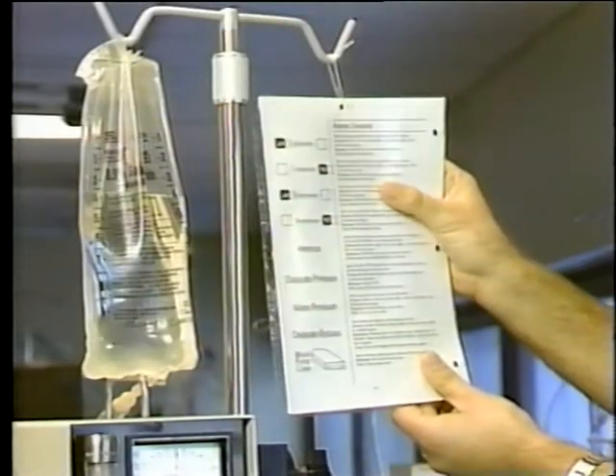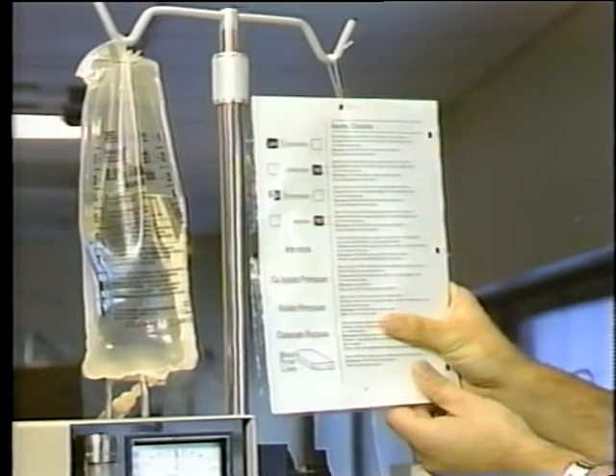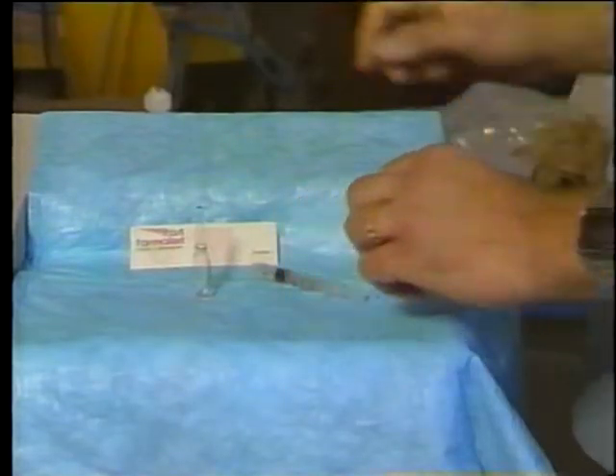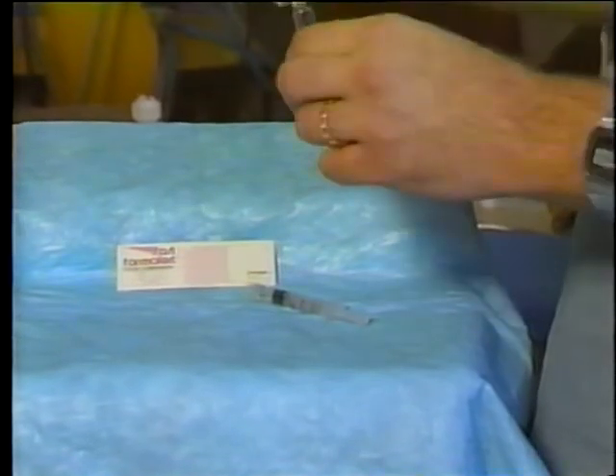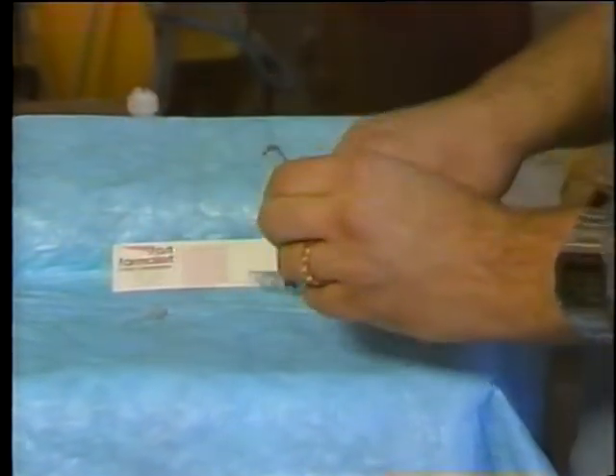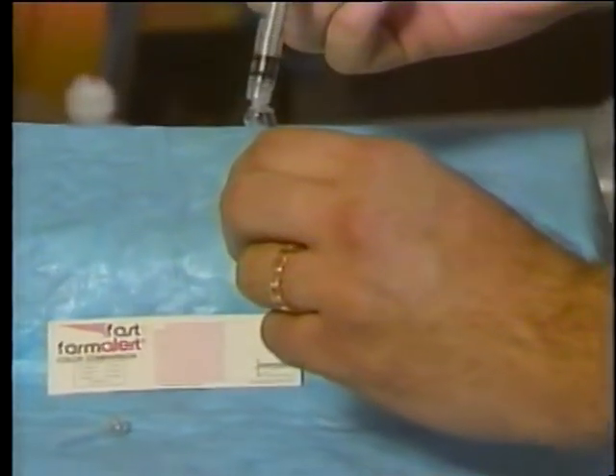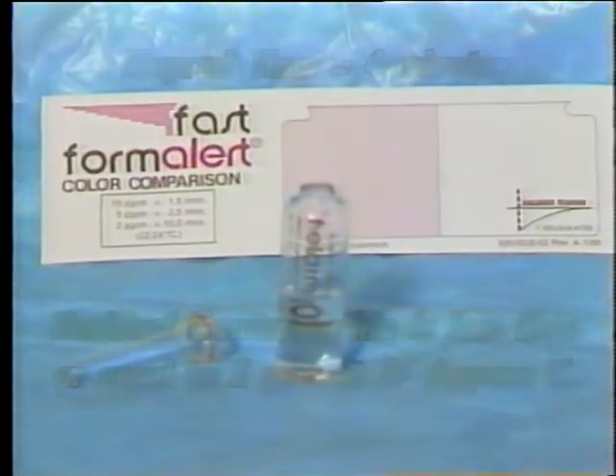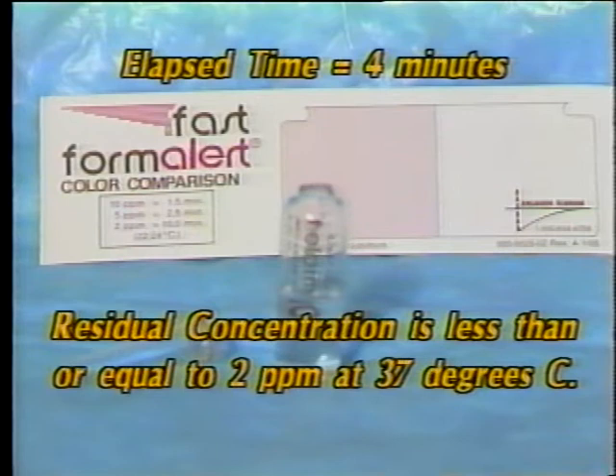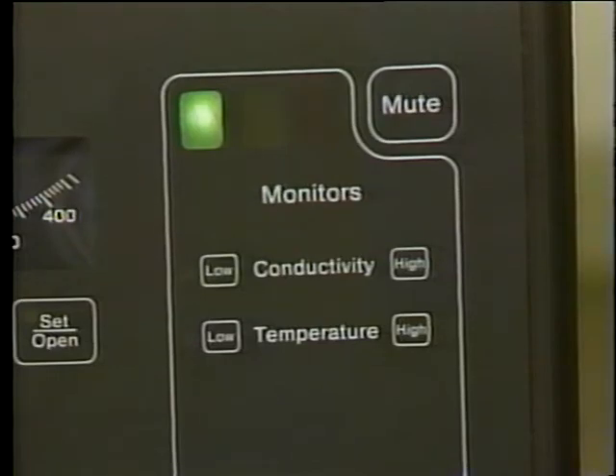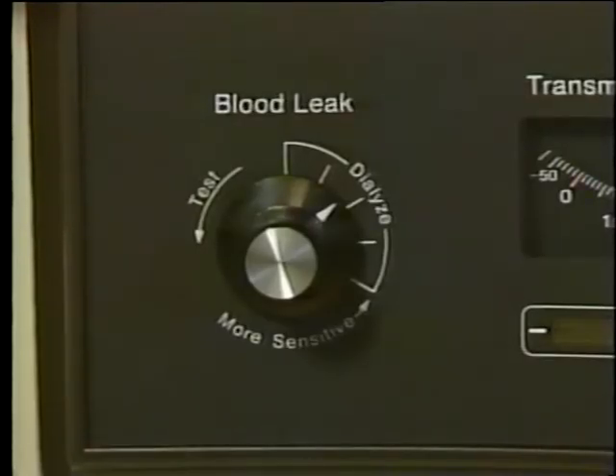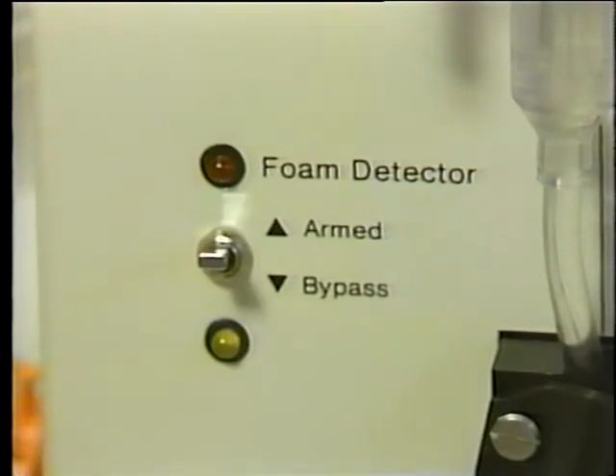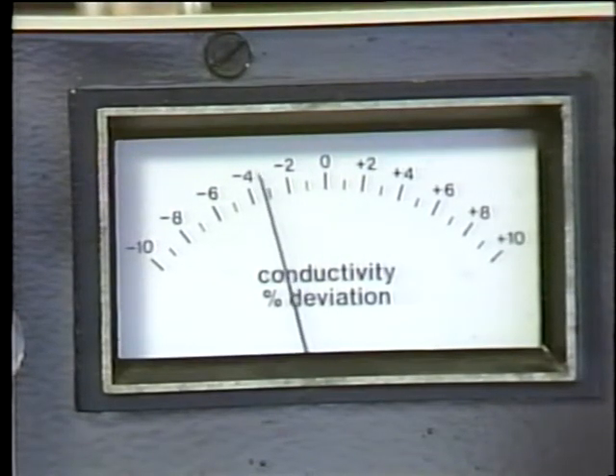Completing a pre-dialysis checklist will ensure that the system is functioning properly prior to the start of a treatment. The initial check is to verify the removal of disinfectant from the dialysate delivery lines. The next item in a pre-dialysis checklist is verifying monitor performance. While the human body is remarkably sensitive, we should never rely on the patient's condition to let us know that the machine is not working properly.